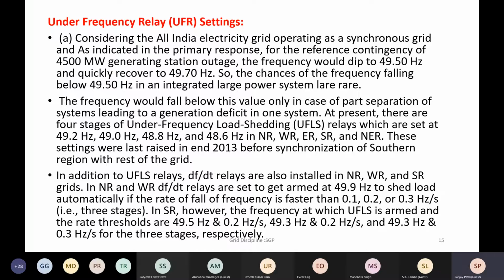On the distribution side, basically 33 kV, 22 kV, 11 kV, etc., the actual load can be shed in coordination with the frequency control. Basically, the load and generation balance can be achieved either by controlling the generation or controlling the load. So the under frequency load shedding schemes are accordingly devised, and you all must be aware there are purely under frequency based load shedding schemes. There are also under frequency schemes based on the rate of change of frequency, dF by dt. Some of the details given here are based on the experience in the interconnected power system of India. The rates could be 0.1 hertz per second, 0.2, or it can go to 0.3, 0.4 hertz per second.